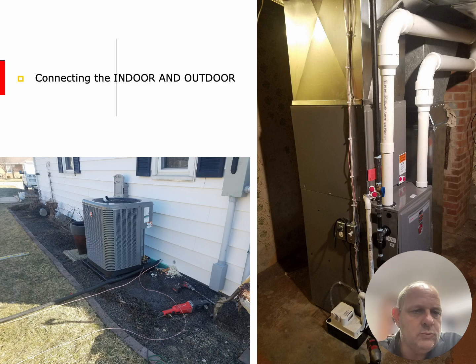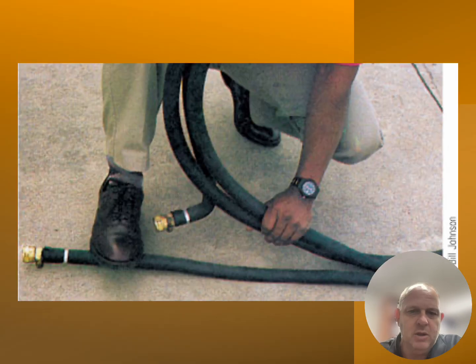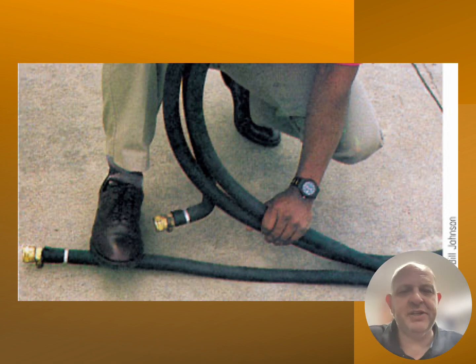The way that you straighten out a coiled line set is to take it from the outside of the line set, step on it, and then walk your way, rolling that line set as you go. And that's going to give you a nice straight line set that's not going to kink on that unit itself.